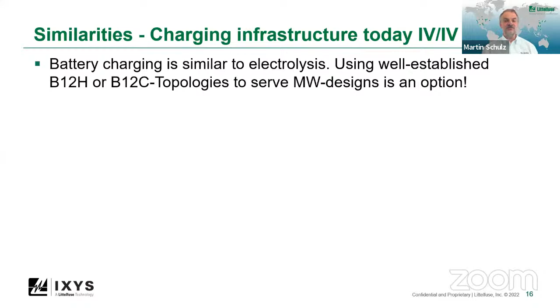Use a specially created medium voltage transformer and use a B12C topology, thyristor based, and instead of electrolysis, power your batteries. It's the identical application, it's the identical control. The question is how many cells you need to put in series to get to the voltage level you target. This is a single stage energy conversion application, and in turn it's the most efficient one you can build.